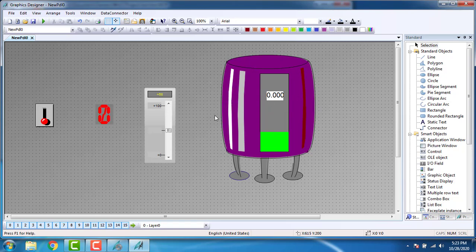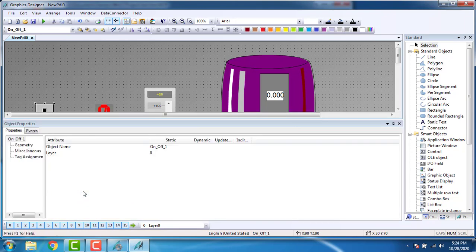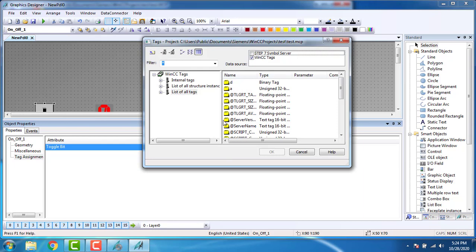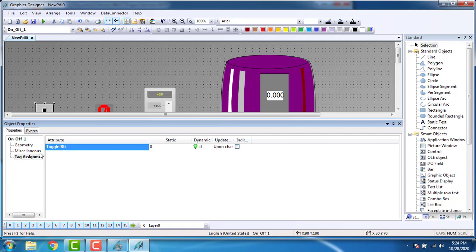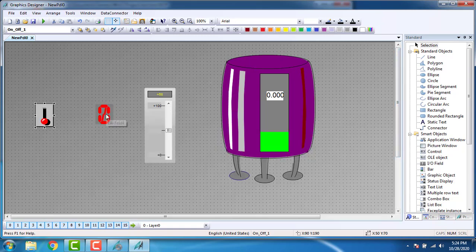First, we have to define the digital elements. So right click, then Properties. You can see the tag assignment — toggle bit. You can see the bulb structure dynamic. Right click and go to Tags. Select the digital tag 'D'. The update will be upon change. Click OK. Close it. Now we have the value display — the digital value display. Right click on the value display, Properties. Go to Output/Input, right click on the output value, Tags, select the digital tag 'D'. OK. The update will be upon change. Close this.